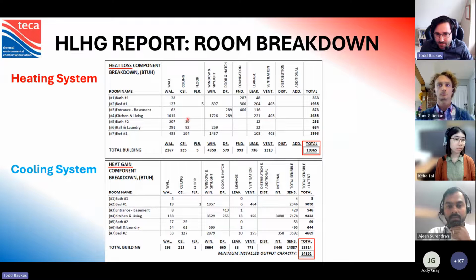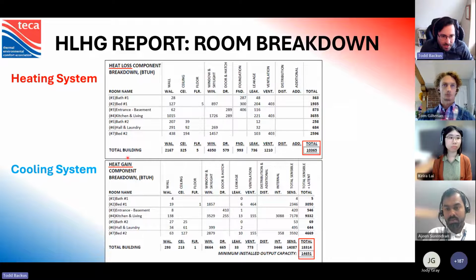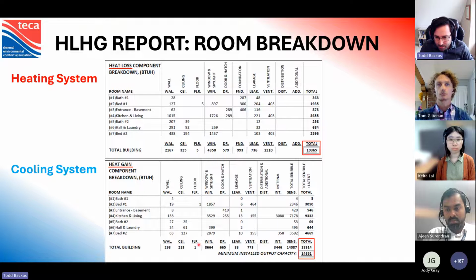But this is an excellent way to check your numbers too, because if you see one of these numbers that's just sky high, that's a good indicator that maybe you've hit an extra 0 when you were calculating the area of, say, a wall. Now coming down here at the heat gain component breakdown, same thing. We have it broken down room by room, all the wall, ceiling, and whatnot. Again, on the heat gain side, windows are even more dramatic because you have that solar gain. And actually in this example, the walls are not bad at all. The next highest is actually the internal loads.